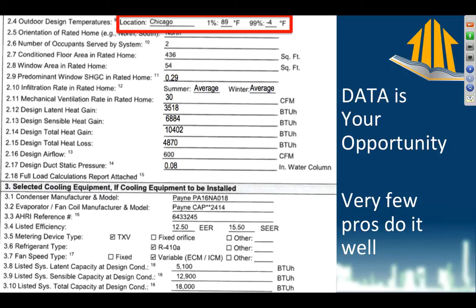Ridiculous. So what we want to do is pick the 1% and 99% values, which are actually in the manuals for Manual J and for ASHRAE. The second thing to look at is the number of occupants served. This is generally the number of bedrooms plus 1. So if this piece of paper says 2 people live in this house, we'd assume that means there's 1 bedroom with 2 people in it.